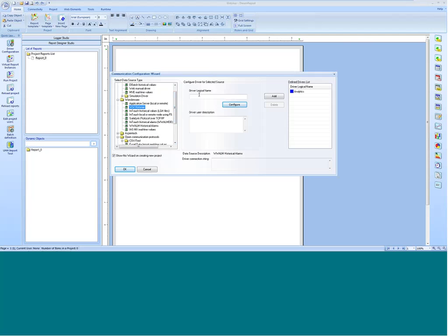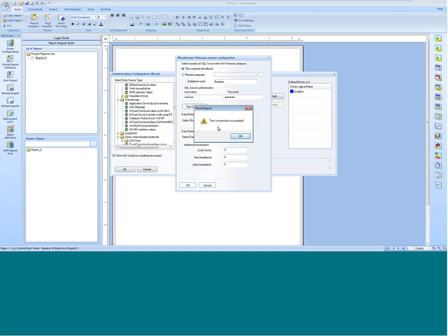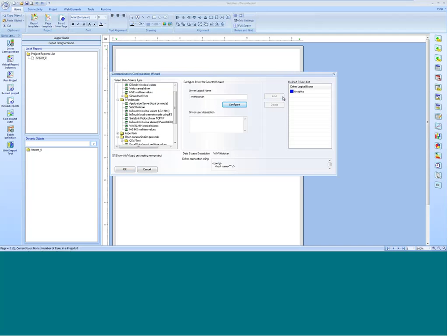For today's illustration, we're going to use the Wonderware Historian. I'm going to give my driver a logical name called WWHistorian and click Configure. I don't need to enter a remote computer name since the historian is on my local computer. I'll put in my SQL username and password to connect to the database, then click Test Connection. I've got Test Connection succeeded, so I'll click OK and Add. I've now added that to my defined driver list and will be able to browse the tags in my Wonderware Historian for reporting.